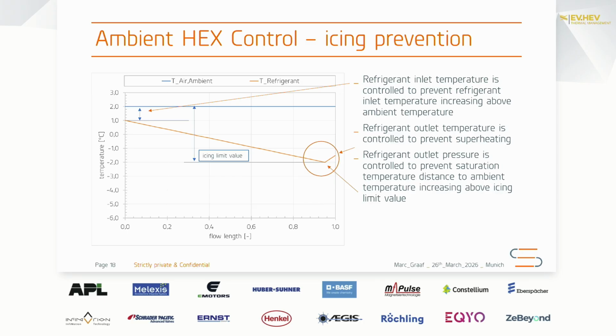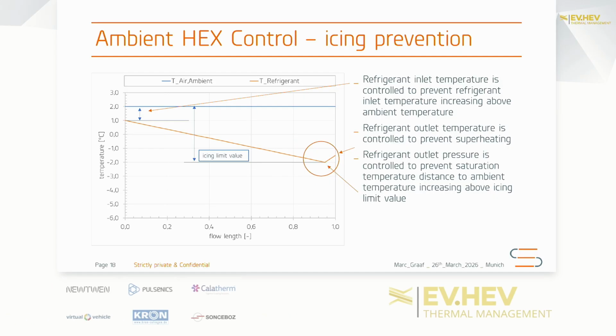If you do it the right way, you have a very small superheat, and your refrigerant temperature is always below, let's say, the ambient temperature over the complete surface of the heat exchanger. Why do I show this here? Because this characteristic of how this line drops depends on the refrigerant. So if we allow a temperature difference of 5 degrees for YF or 134A, that means only half a bar pressure drop. But for a CO2 system, half a bar pressure drop is only 0.5 Kelvin.